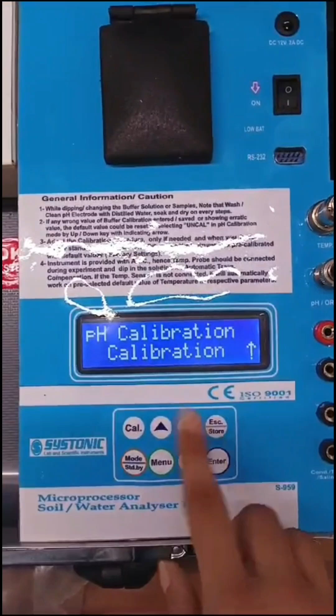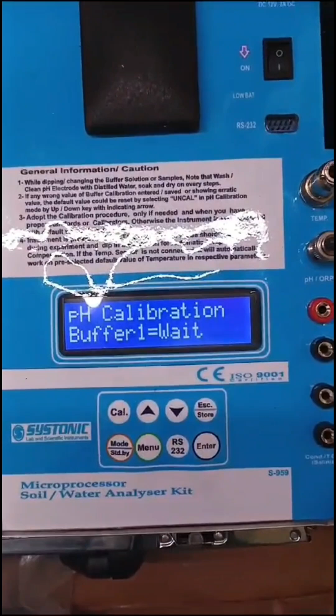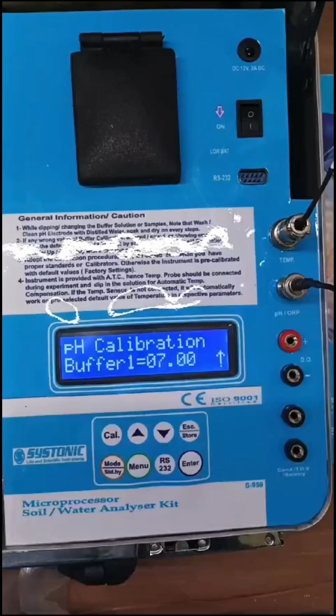Now again go to cal and to pH, enter. For the calibration, press enter. Now I have dipped the pH electrode in buffer solution of 7. Press enter and wait, and as you can see, it is calibrated. Simultaneously you can do the same process for pH 4 with buffer 2 and for pH 9 with buffer 3. Now we will check the conductivity.